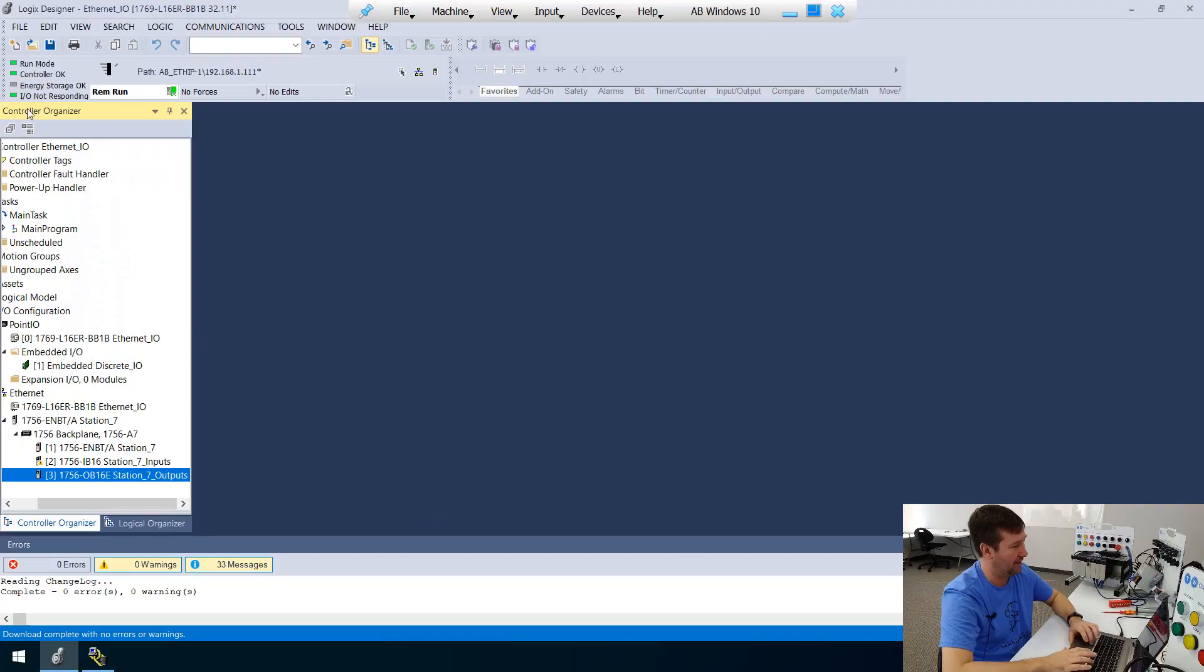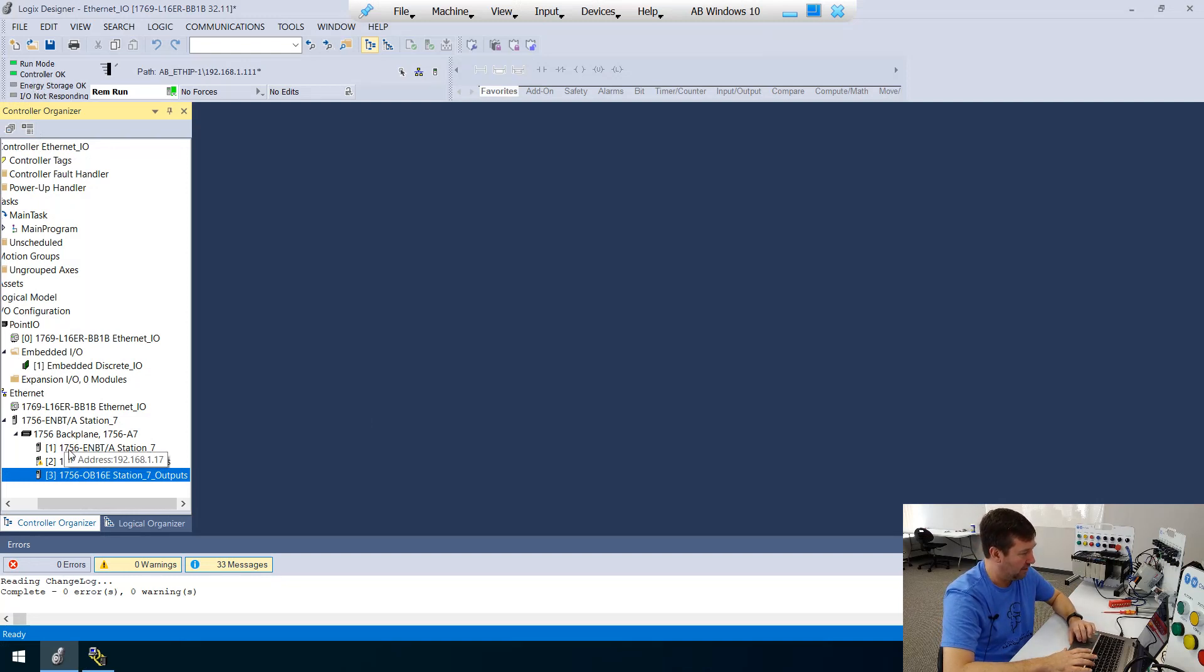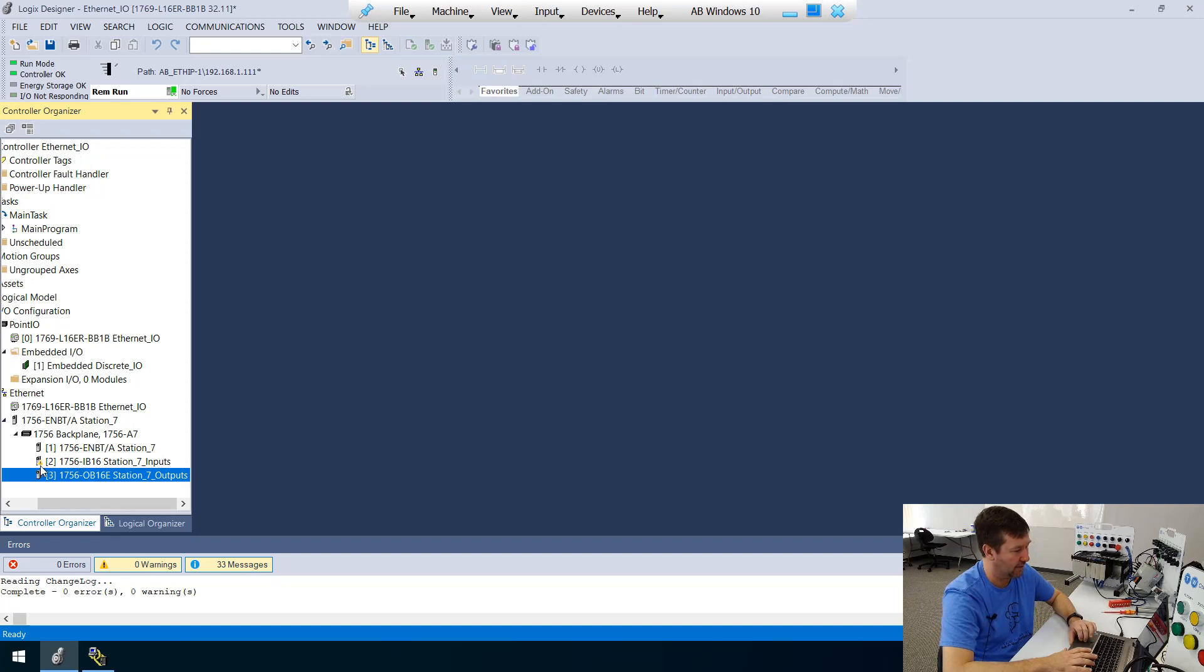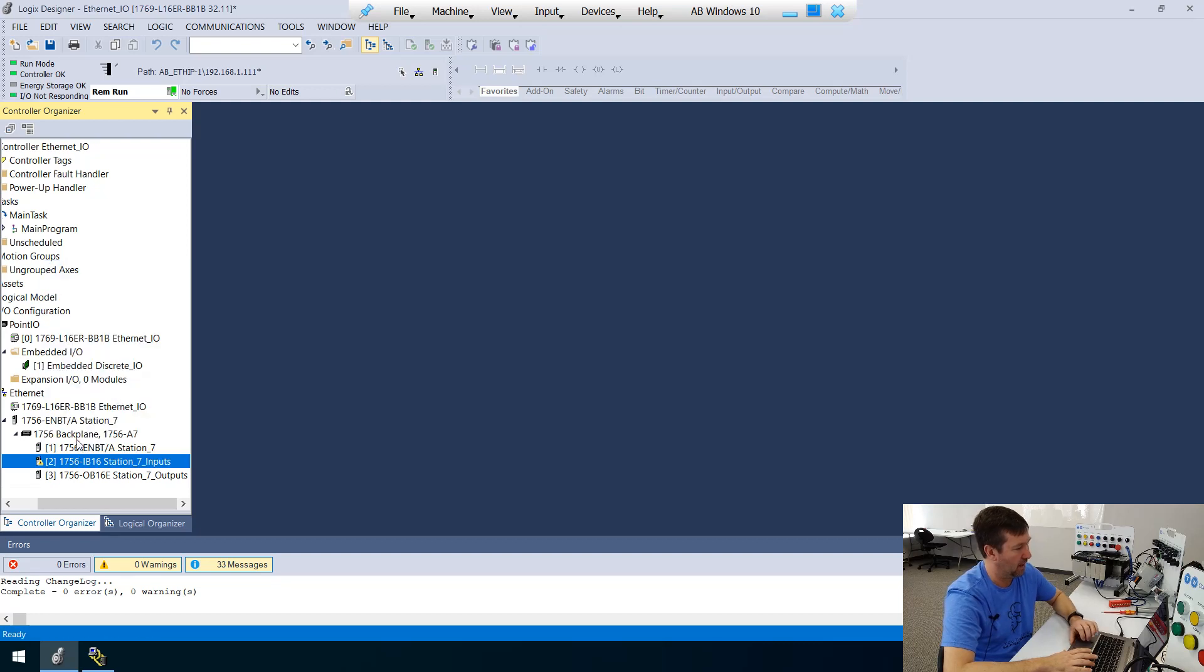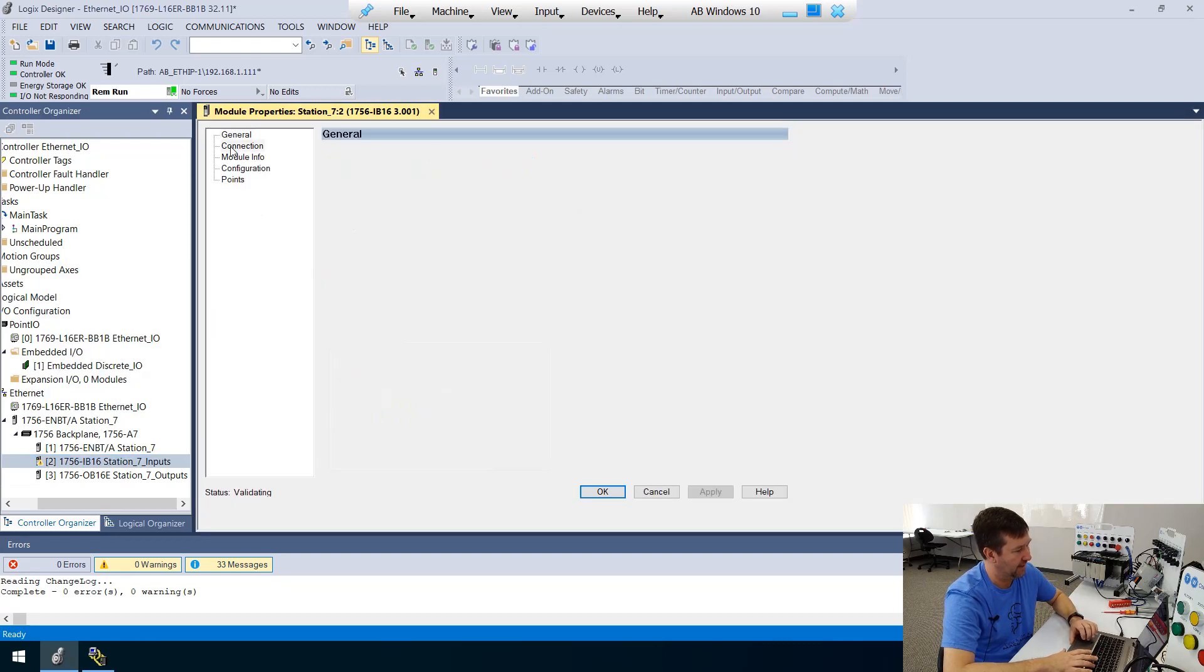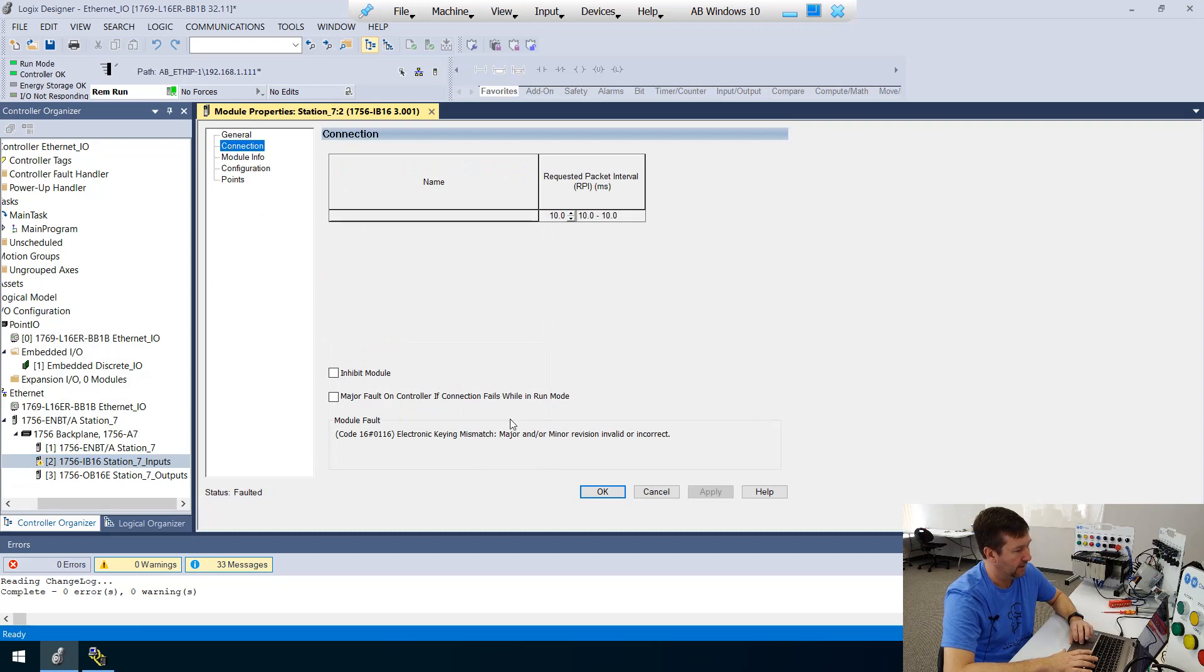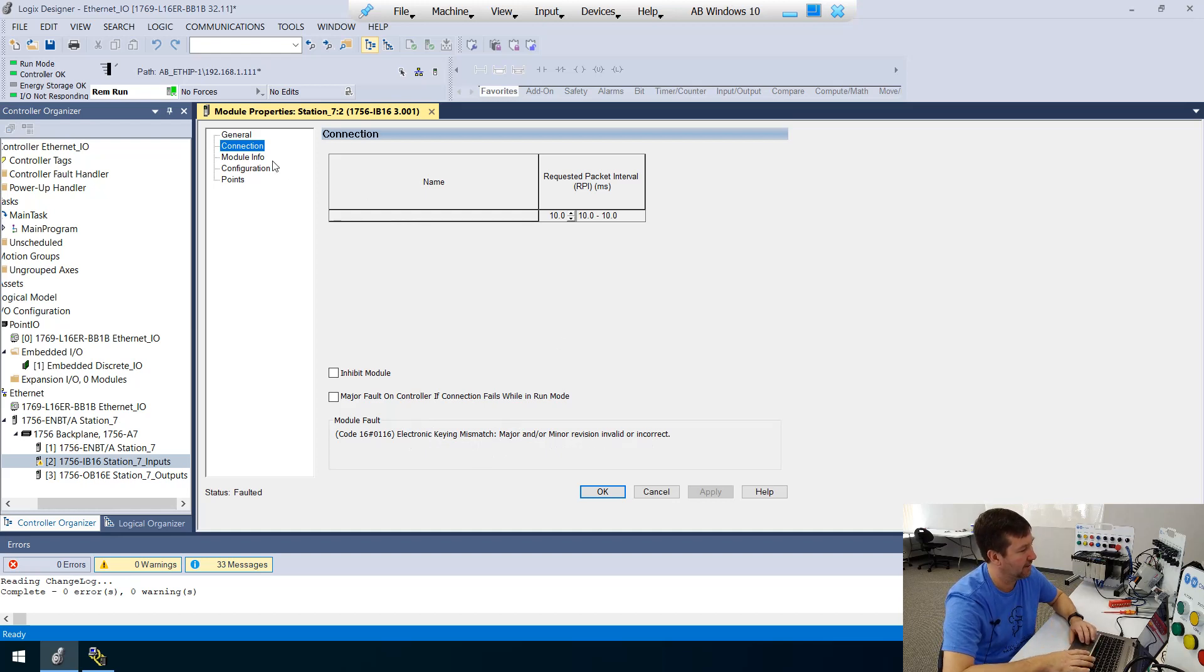The major revision does need to match even on these. And so right now, our IO not responding is on. And if we look down through our IO configuration slot two, that IB16 has got a little yellow triangle by it.